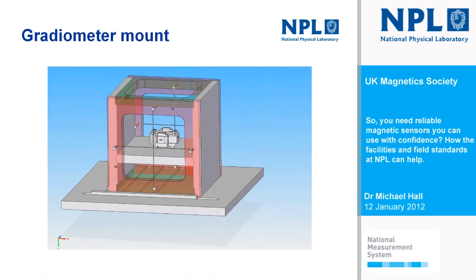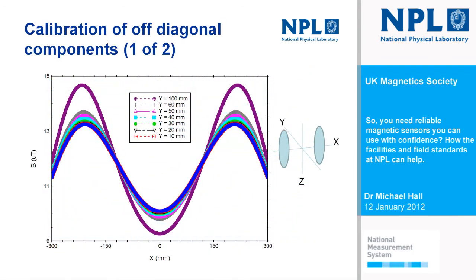So that goes inside the gradient coil, inside the 3-axis Helmholtz coil system, and actually it can also go inside of a Helmholtz coil system to apply biasing fields, which are also important. So let's have a look here if we have this set up as a Helmholtz coil to look at these off-diagonal components. You can see here now that we don't have, as you would have for a gradient coil, a nice linear field with distance. We have considerable variation of field with distance. If we just focus on the region around x equals 0 and make a plot against these different y positions of the field that we get, the result is shown in this next slide, where we can see that it's not in any way linear, but it's varying nice and smoothly with y position.